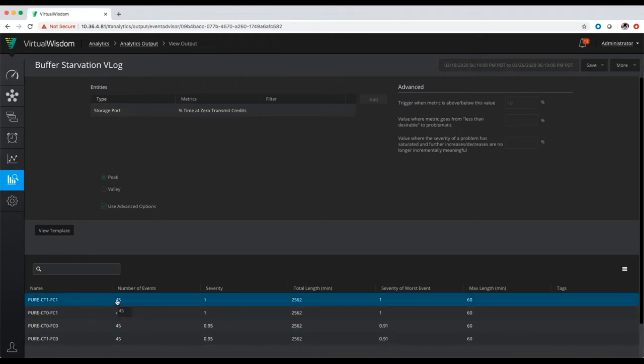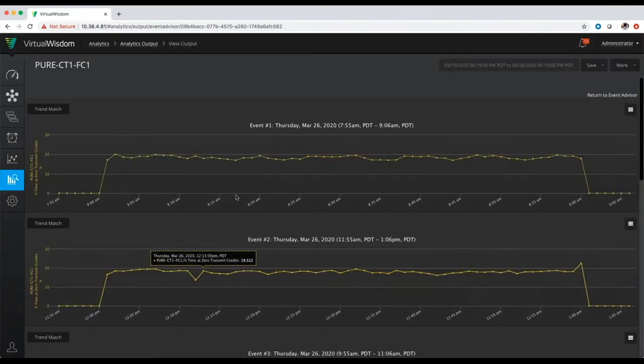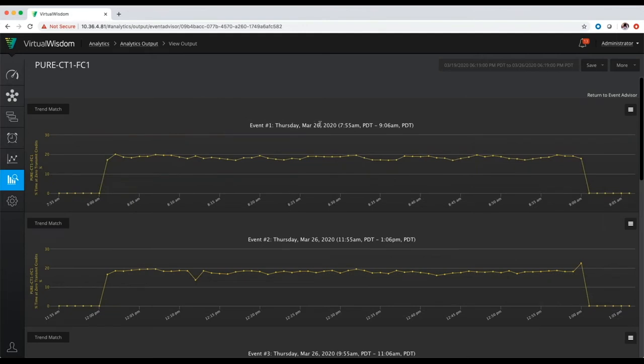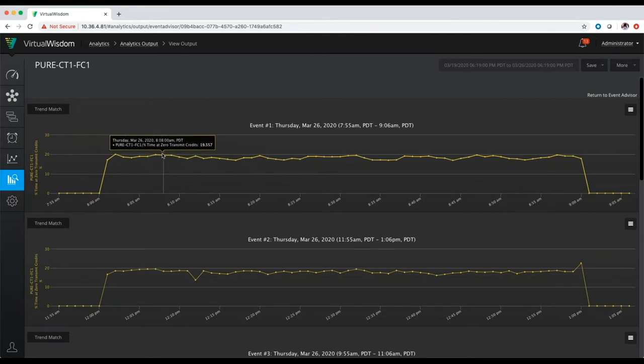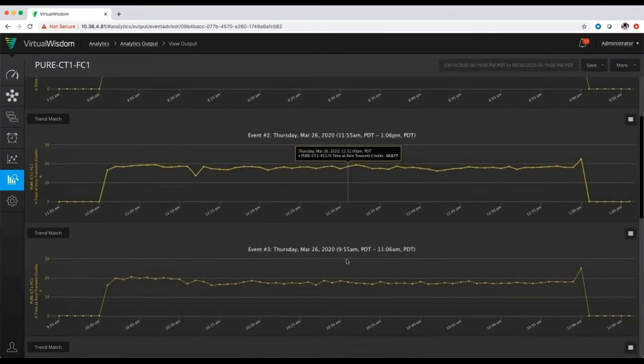You can see it's the exact same four ports that we saw when we were looking at the report. If I click on this particular event, it will take me into that particular event and it'll populate what it sees for those trends. You can see that event number one was on Thursday, March 26 at 8 a.m. — we were having normal flow control and then we jumped up to a little over 20 percent. On Thursday, March 26, we had an event at this particular timeframe and so on.